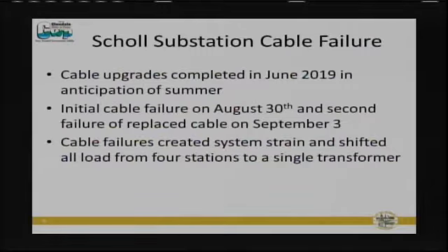And that was where we had a cable failure at our Scholl substation. When we investigated this initially, we had first the cable failure on the 30th. We replaced that cable and it failed again on the 3rd. When we came back out to look at this, we found a couple of things that we didn't initially see when we went to the substation. The cable failures themselves created system strain, took away that contingency we had. We didn't have an N-1-1 in this particular case, so we didn't have that double backup for this particular set of substations.